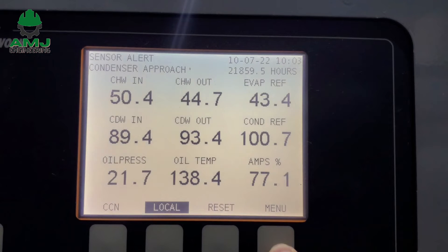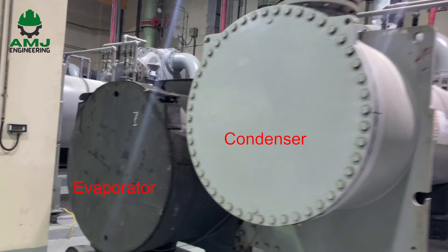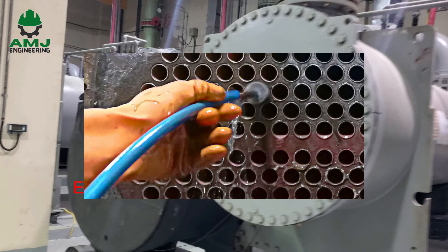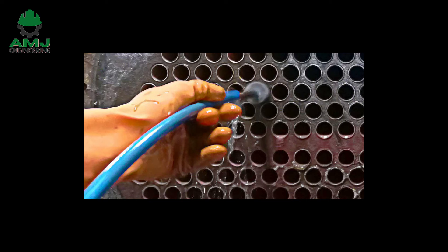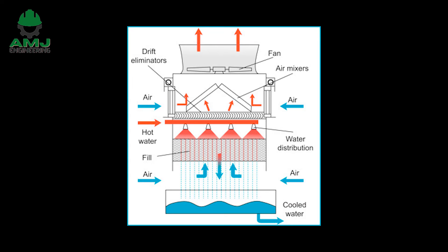What does high approach mean? It means the chiller condenser has gotten dirty and requires cleaning. The condenser approach raises much quicker than the chiller evaporator approach because it is an open piping system, so a lot of dirt gets inside from the cooling tower. Thus, it is very common that the chiller condenser approach rises above 7 degrees Fahrenheit, causing poor chiller performance and high power consumption issues.